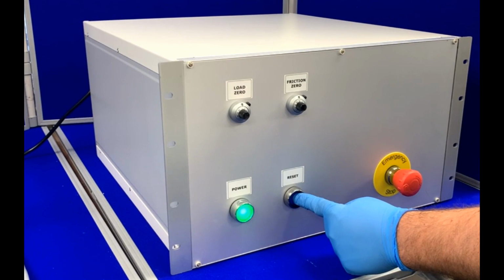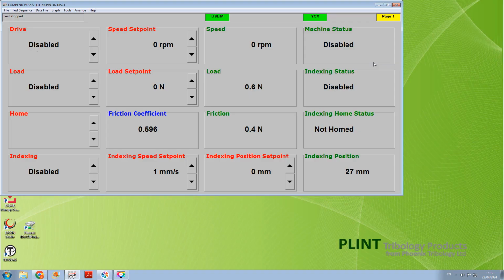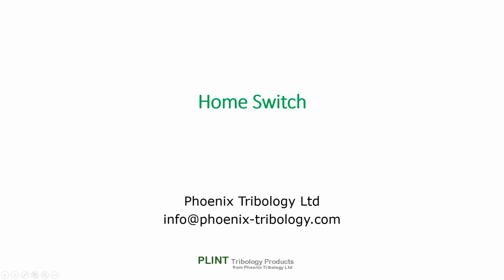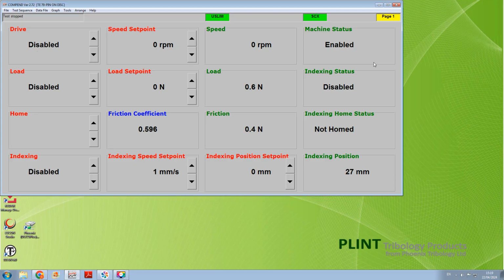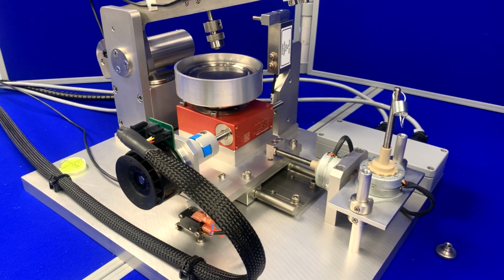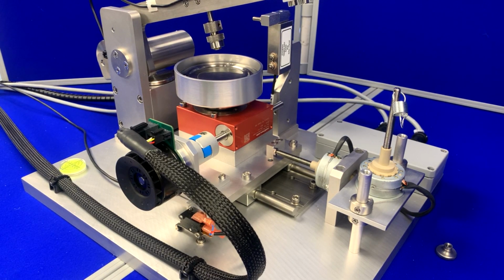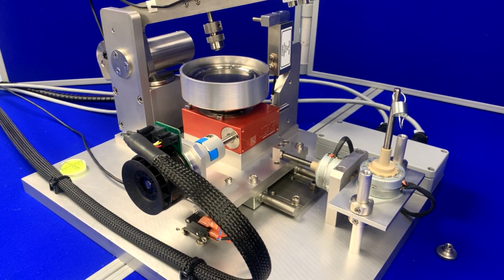Press the blue reset switch on the instrument panel. The machine status box on the screen changes from disabled to enabled. Before using the machine, the linear slide requires a home reference point. Press the up arrow next to the home box. The stage will motor to the right until the home position is detected. The indexing home switch status box on the screen changes from not homed to homed.